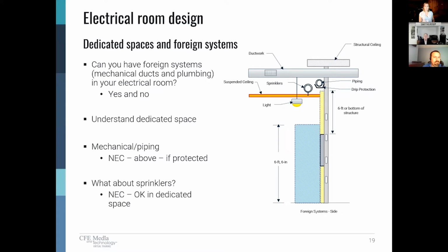It really is whether they're going over the dedicated spaces, and whether they're isolated by distance, a structural ceiling or a suspended ceiling, so that it's not dripping on the gear, it's not impeding entry into the gear for working space, not necessarily maintenance, but future access space. And sprinklers, another common thing. Sprinklers are the one thing that you are allowed to have in the dedicated space. This is different from ducts or a drain running through or a plumbing line, which generally is not good practice to put in the dedicated space, but have to be located above it per NEC. Sprinklers are allowed. We're going to talk a little bit also about best practices with regards to this.